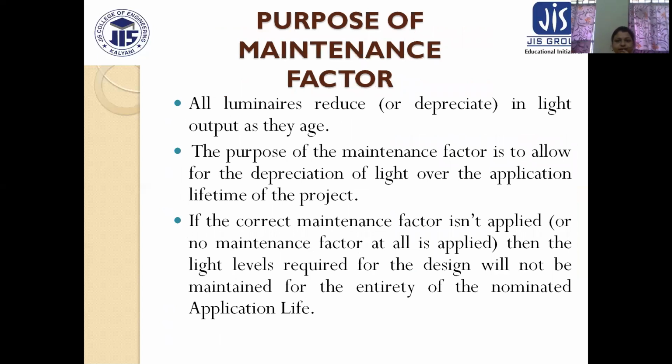Now, the purpose of maintenance factor. All luminaires reduce in light output as they age. The purpose of the maintenance factor is to allow for the depreciation of light over the application lifetime of the project. If the correct maintenance factor is not applied, or no maintenance factor at all is applied, then the light levels required for the design will not be maintained for the entirety of the nominated application life.